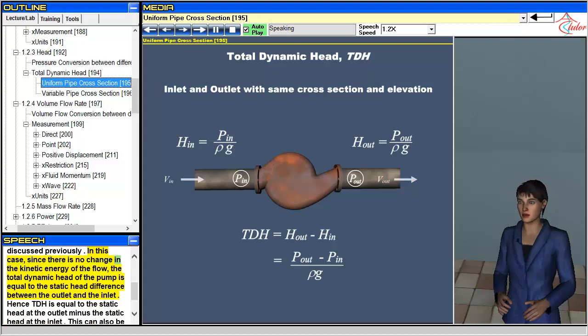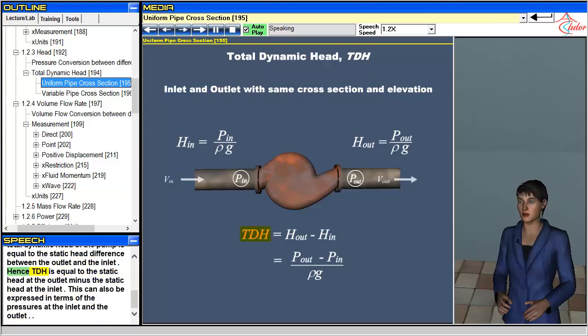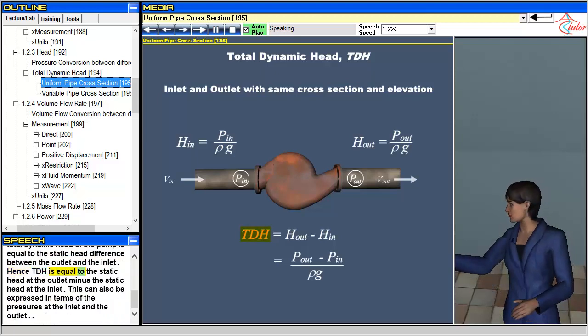In this case, since there is no change in the kinetic energy of the flow, the total dynamic head of the pump is equal to the static head difference between the outlet and the inlet. Hence TDH is equal to the static head at the outlet minus the static head at the inlet. This can also be expressed in terms of the pressures at the inlet and the outlet.